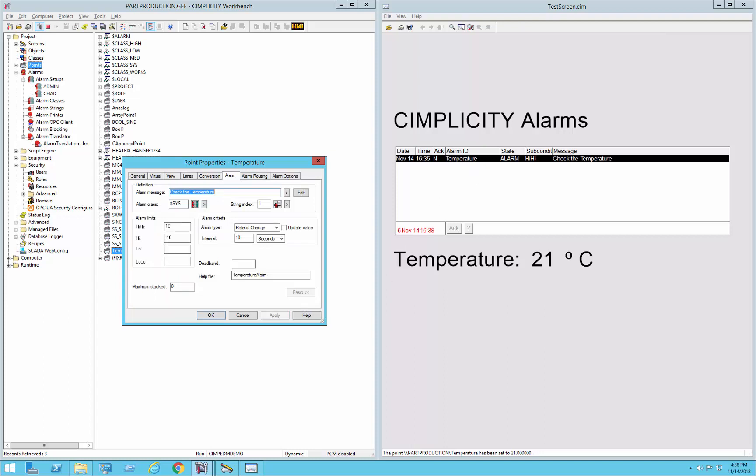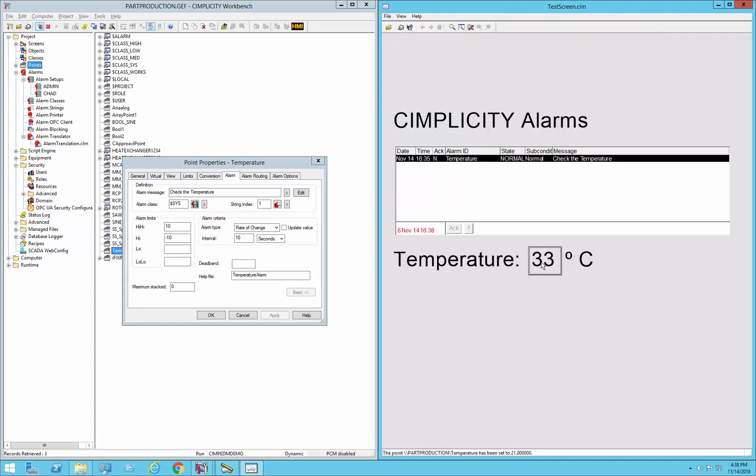You can see that it was originally high high, but now 10 seconds went by and it realized that the value hadn't changed from 21 to anything else, so the rate of change was 0. If I were to indicate 33 here, and then the 10 second interval will come up, we'll see that it will detect that we went up by more than the rate of change. See, high high.